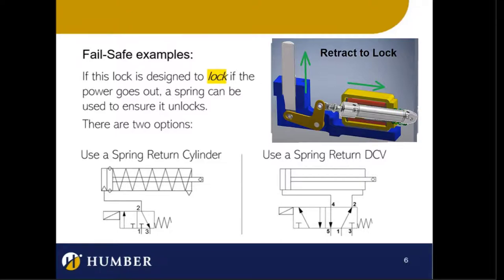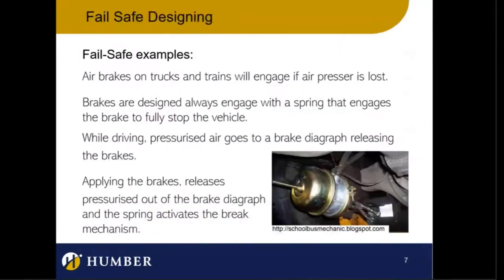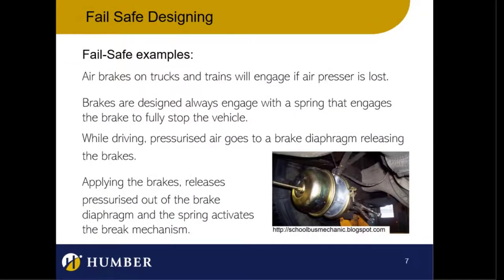This is what you've been challenged to do in the lab — add fail-safe to the locking mechanism. Both DCVs are currently single solenoid DCVs. To add fail-safe, you have to change the locking mechanism to a fail-safe DCV that has a spring in it. Then you have to think about the logic of how to make that happen so that if the system fails, the lock will lock.